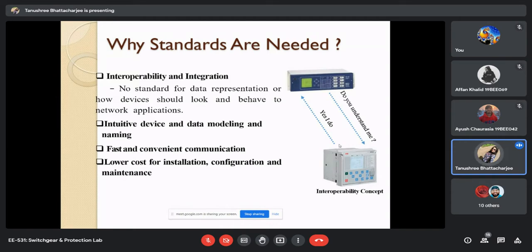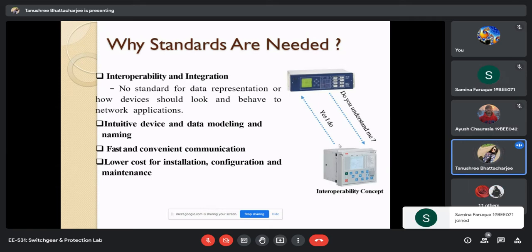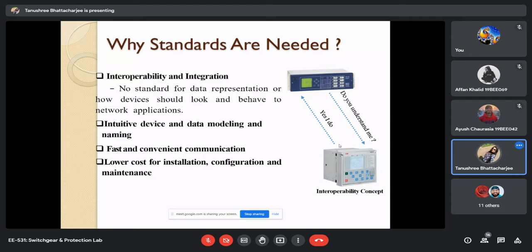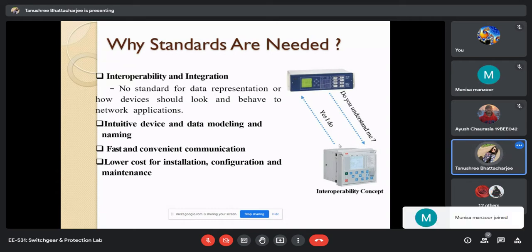A relay can only sense and send its signal to the circuit breaker for operation. But IEDs are computer-operative devices; they can store data, send messages, and communicate with each other, meaning one IED can talk to another, which a relay cannot do. That's why it's called a smart device or intelligent electronic device—intelligent because they have the thinking or decision-making power that relays can't have.